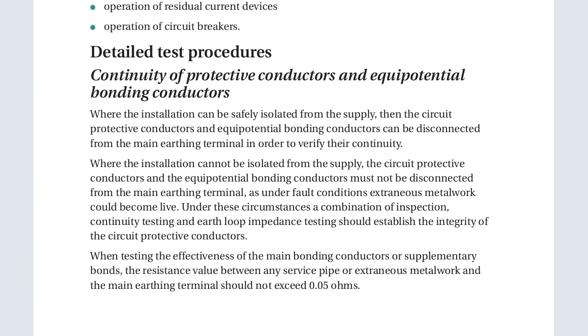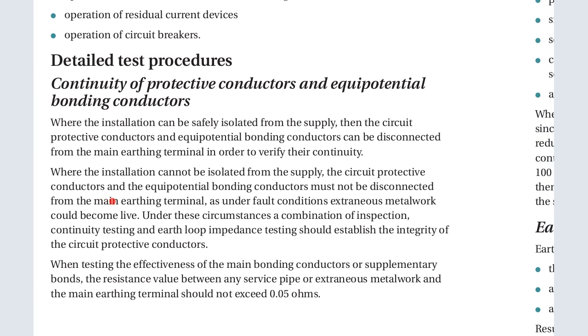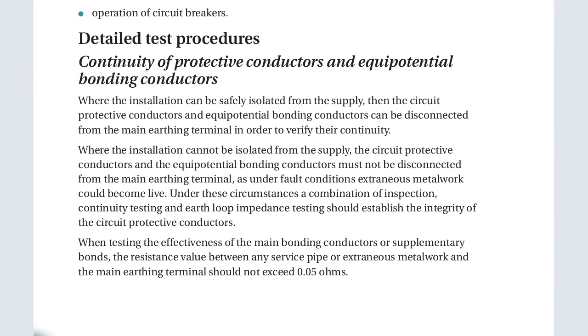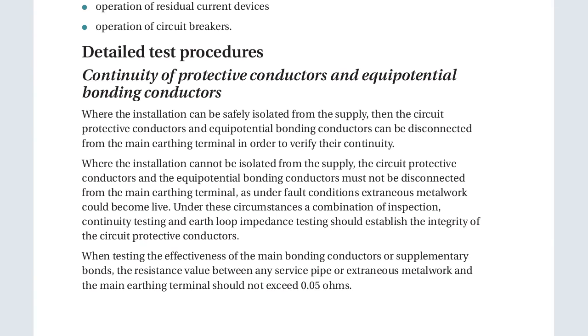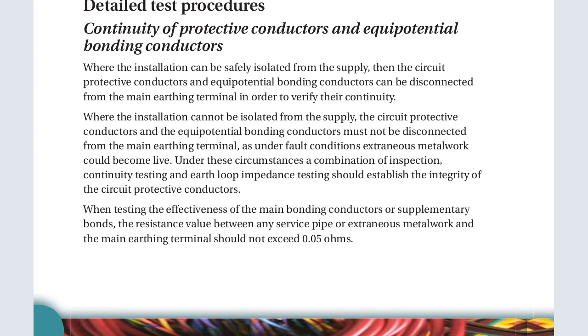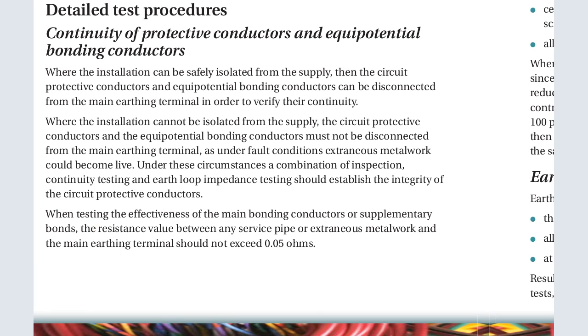Where the installation can be safely isolated from the supply, the circuit protective conductors and equipotential bonding conductors can be disconnected from the main earthing terminal in order to verify their continuity. Where the installation cannot be isolated from the supply, the circuit protective conductors and the equipotential bonding conductors may not be disconnected from the main earthing terminal. Under fault conditions, extraneous metalwork, and we already talked about the extraneous parts, could be live. Under these circumstances, a combination of inspection, continuity testing, and earth loop impedance testing should establish the integrity of the circuit protective conductors.